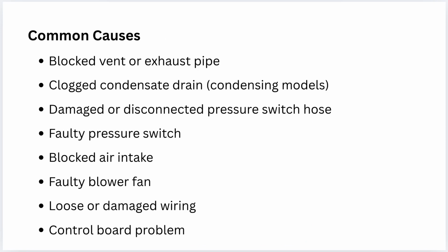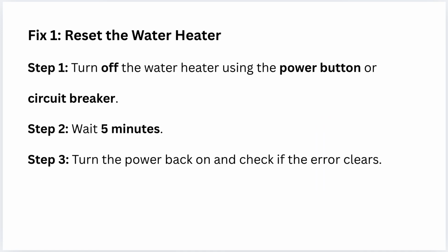Then common causes: blocked vent or exhaust pipe, clogged condensate drain, damaged or disconnected pressure switch hose, faulty pressure switch, blocked air intake, faulty blower fan, loose or damaged wiring, control board problem.